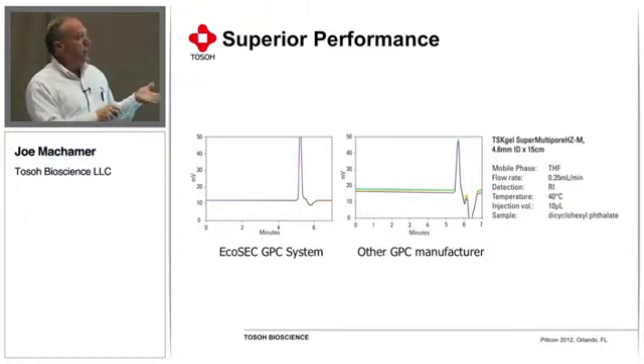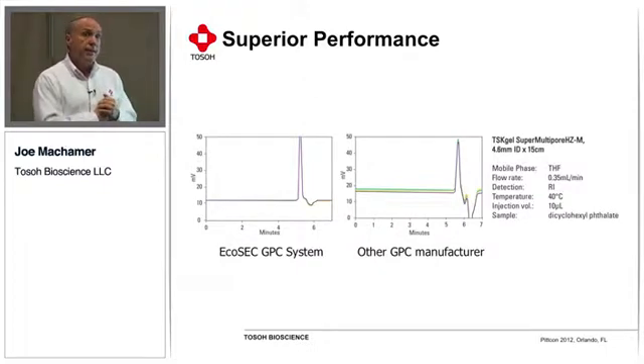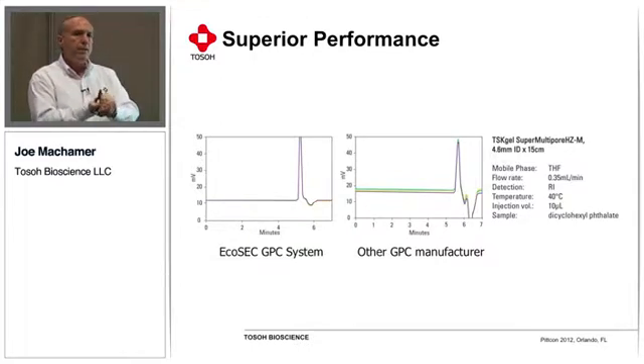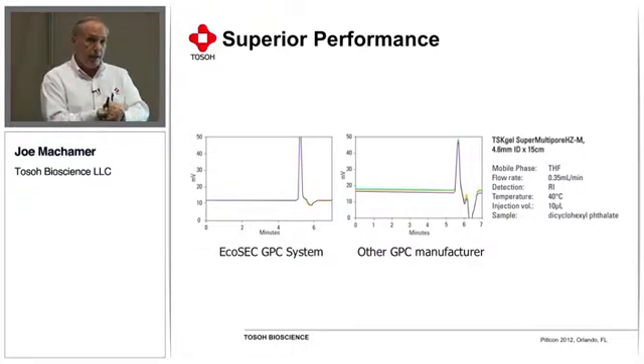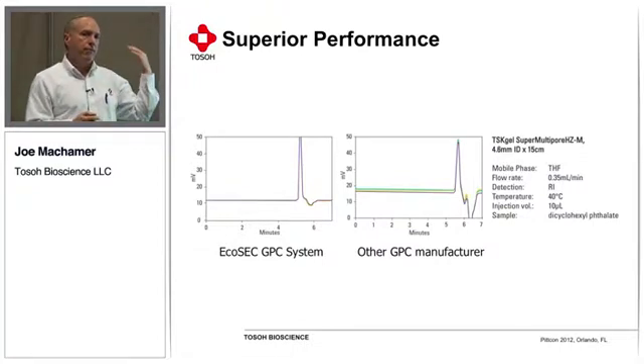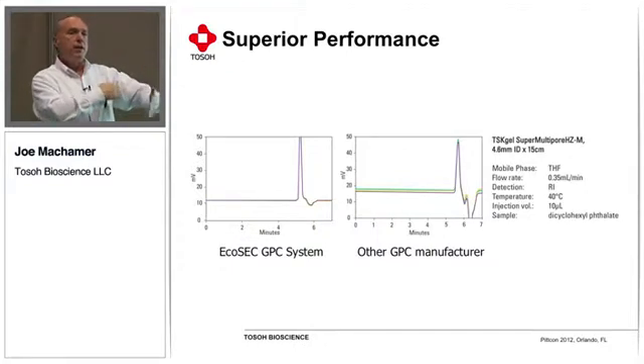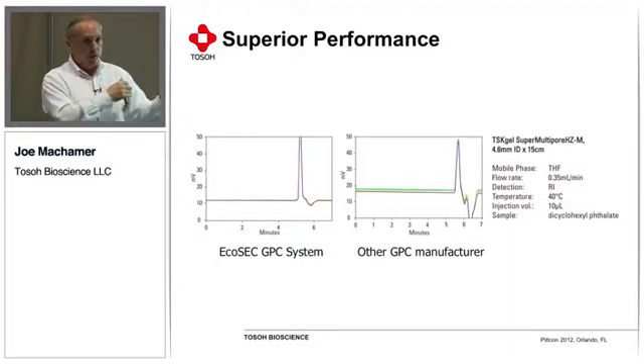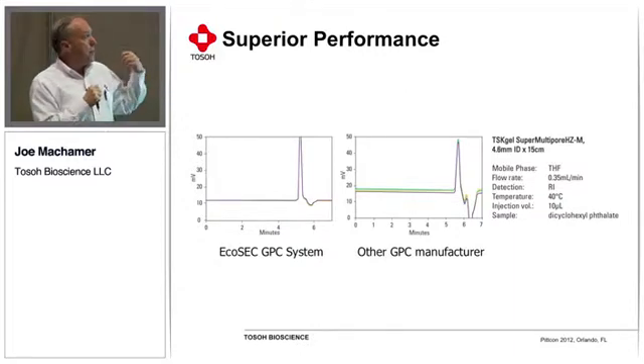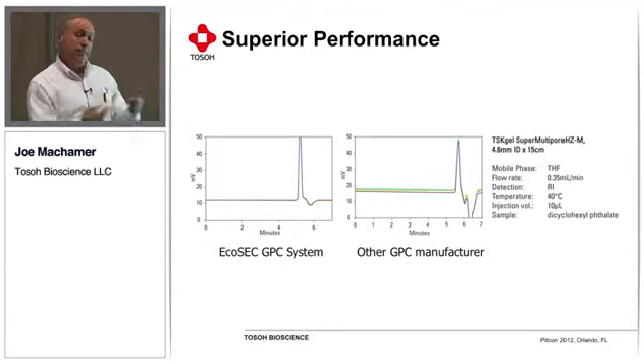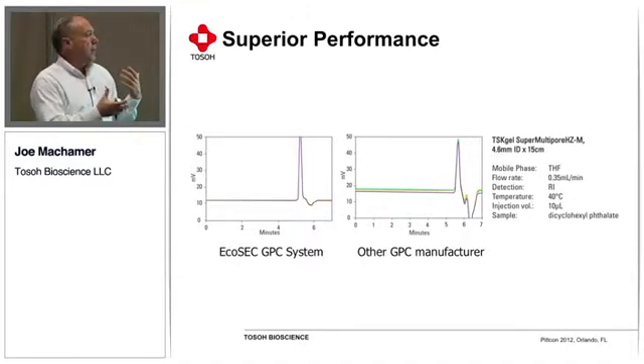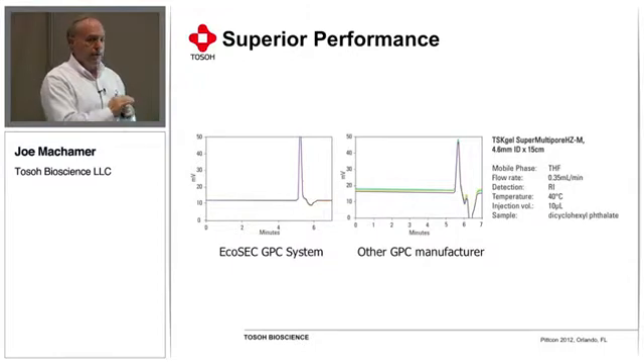And the way this dual flow system works is, in a conventional refractive index detector, the material that's in the reference cell of the detector is not flowing. It's a stagnant pool of THF typically, and as you know, THF will degrade over time. So if you're running samples over a weekend or overnight, if the material in your reference cell is degrading over time, but you have fresh solvent flowing from the column for your samples, there's going to be a continual change in the difference in refractive index between those two materials, which you will see as drift in your chromatography. With the dual flow design of the EcoSEC GPC system, we are continuously flowing solvent through the reference side of the cell as well as the sample side. So we're always able to account for any degradation that's taking place in the mobile phase.